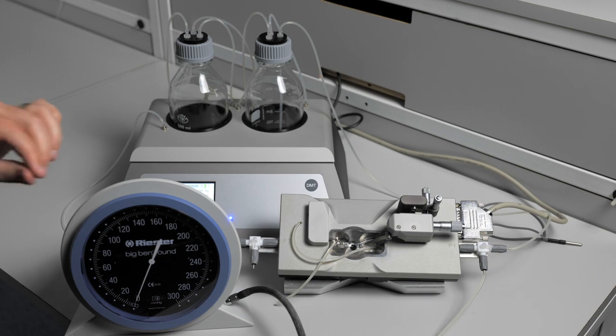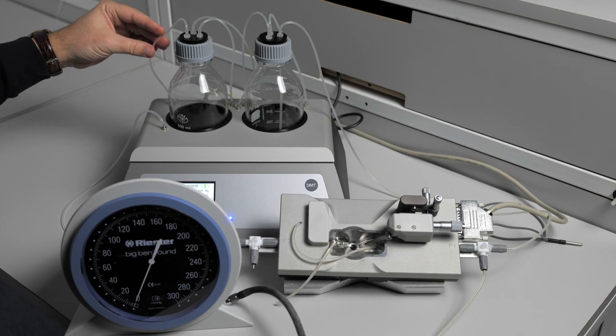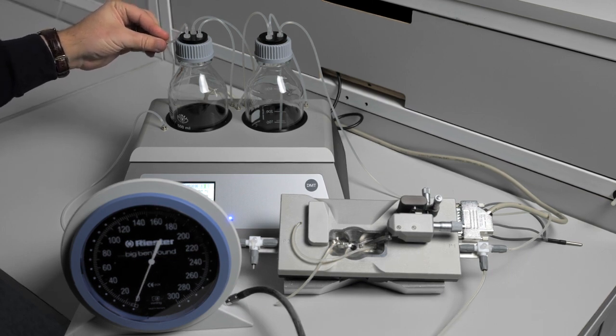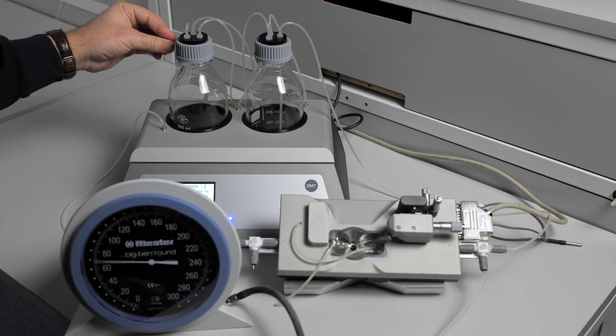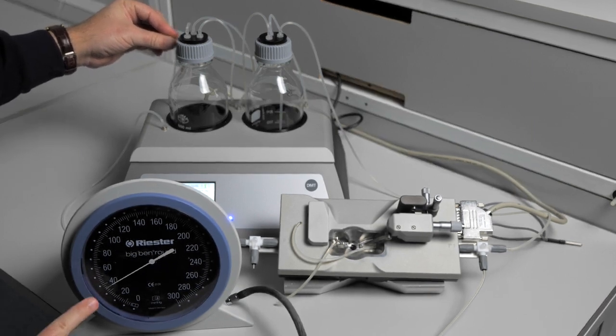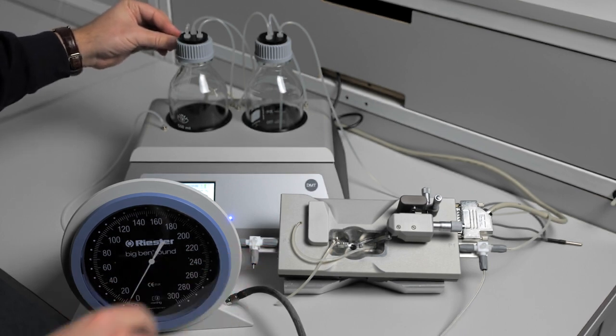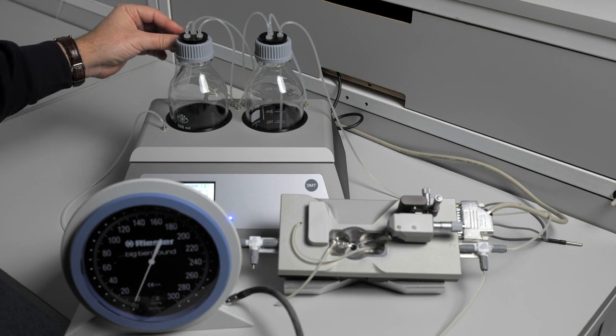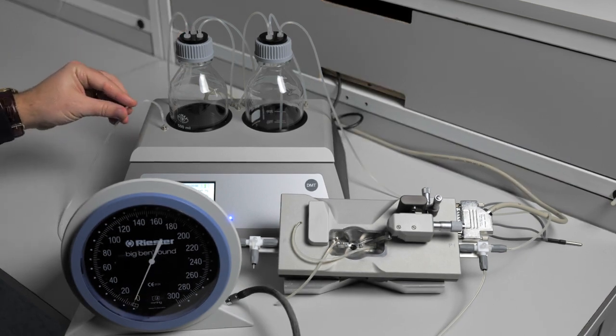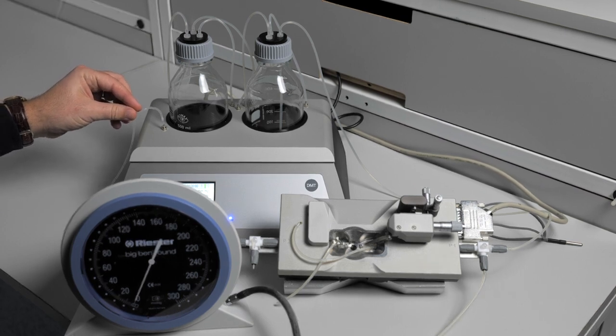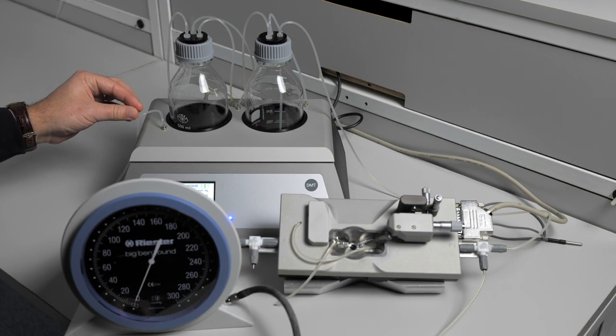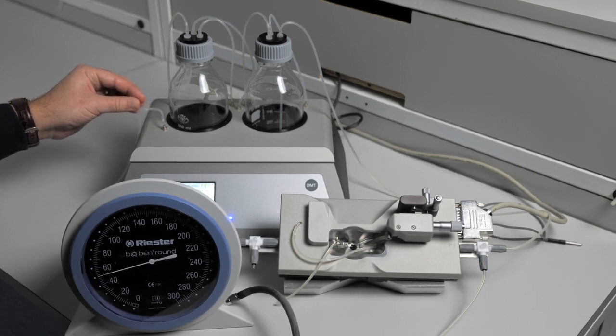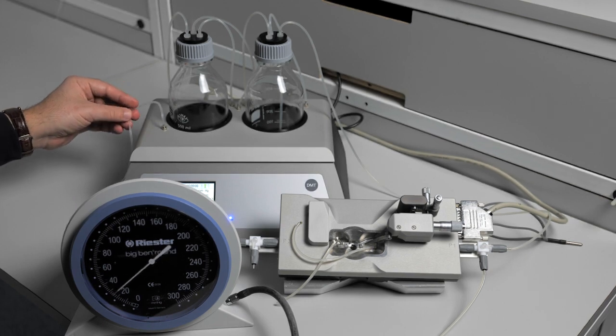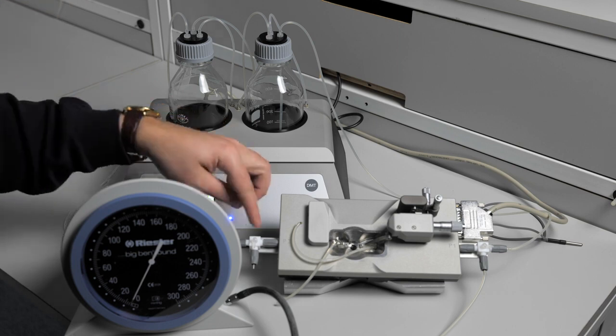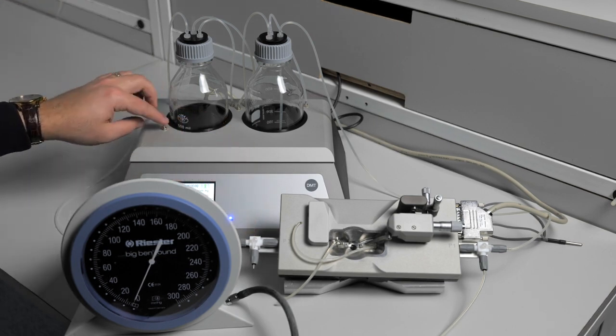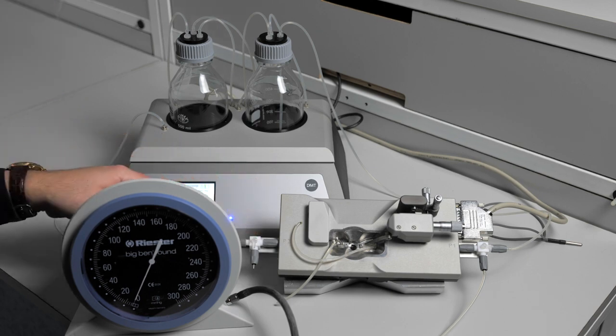To investigate the pressure leak after the chamber, you need to pinch the tubing that's going to the P2 bottle on your interface. Add pressure, and you see that pressure is still falling. We know that the leak is not in the chamber and it is before the P2 bottle. Now we will pinch the tubing before it goes into the interface. Add pressure, and we see that we are still losing our pressure, which means that the leak is not in the interface, the leak is in the tubing or the P2 three-way valve. You can replace the tubing or you can check the P2 three-way valve.